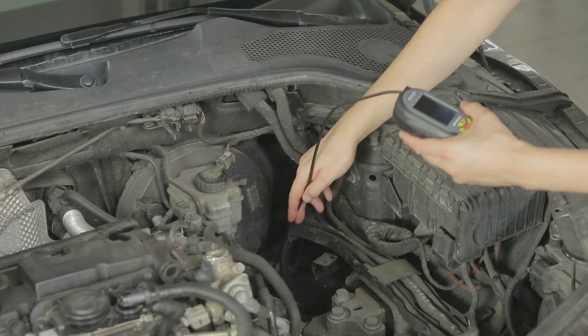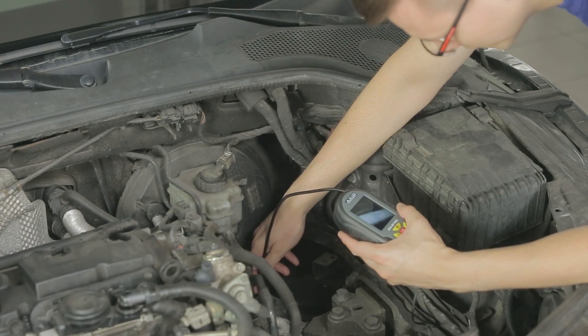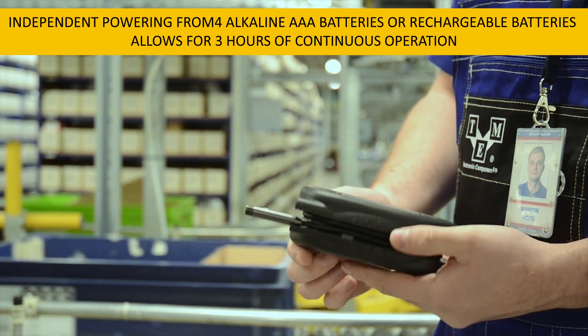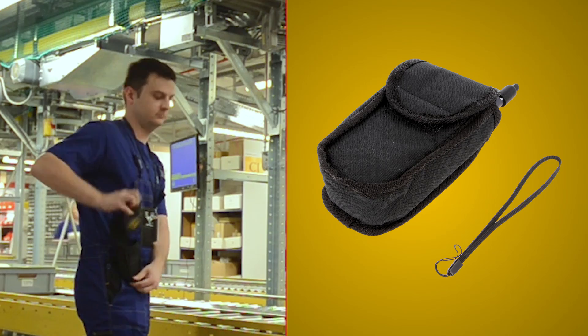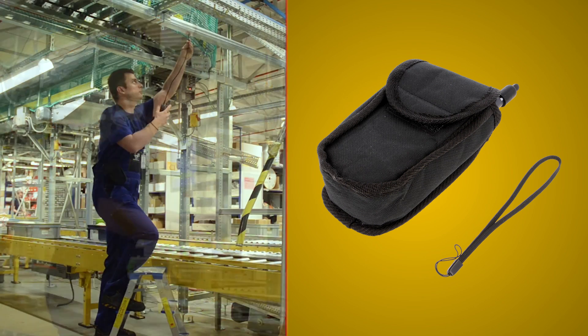The device can be operated with one hand so you can use the other hand to lead the probe. The flexible 60 centimeter probe cable is wound inside the housing, which together with the possibility of attaching the device to a belt enhances the handiness of the Borescope.